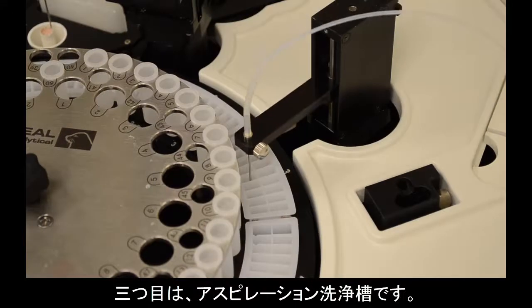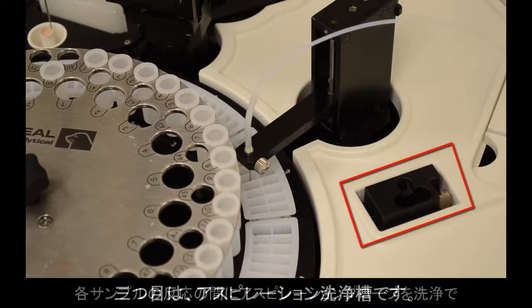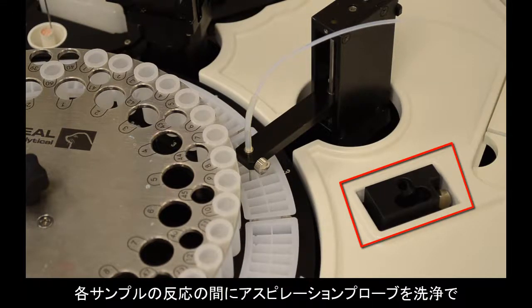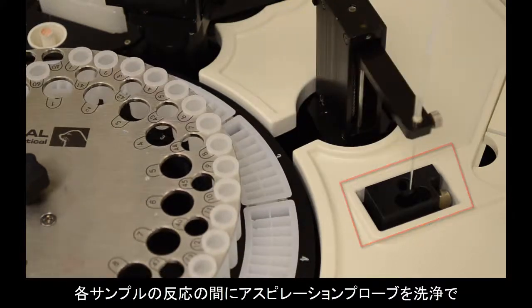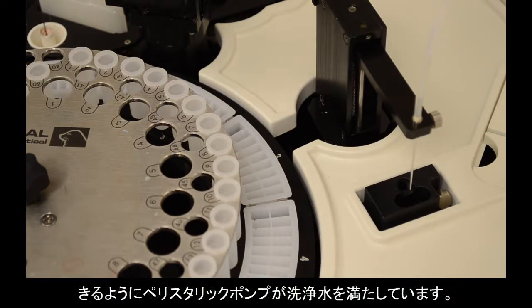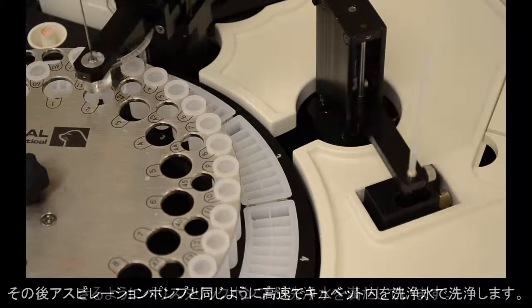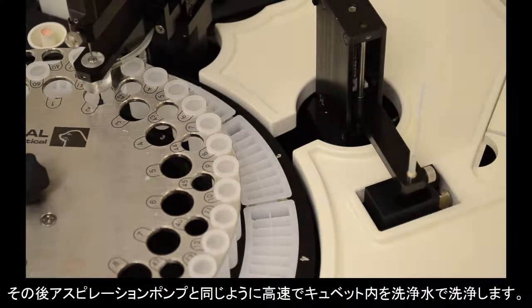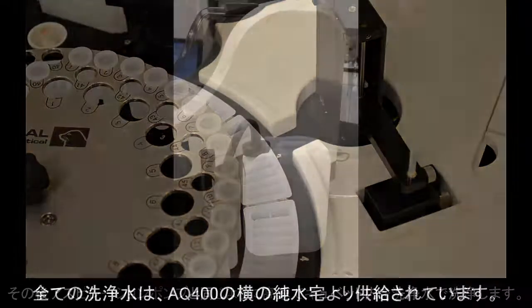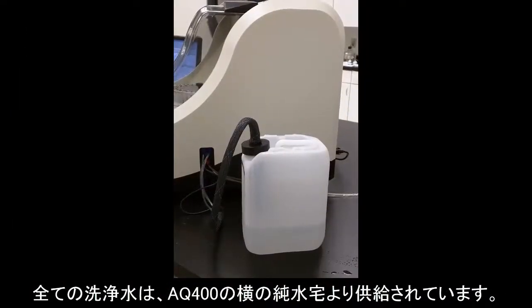The third location is the aspiration wash bath. In between each sample reaction, a peristaltic pump fills the bath with fresh water so that the aspiration probe can dip and wash itself, as well as, with the help of the aspiration pump, provide high-speed flushes of clean water through the cuvette. All of this fresh water comes from a reservoir on the side of the AQ400.